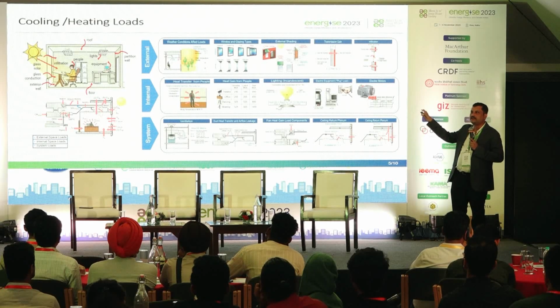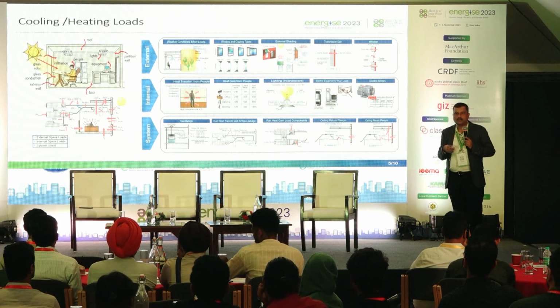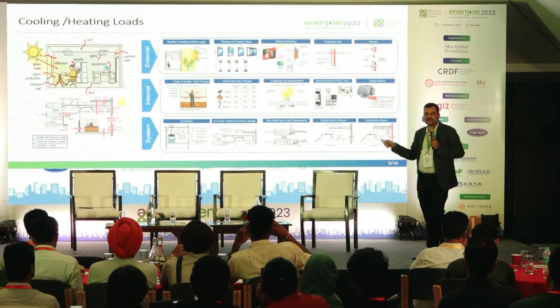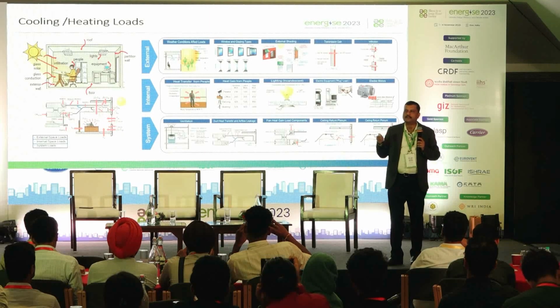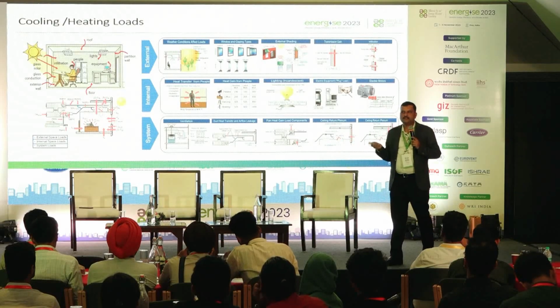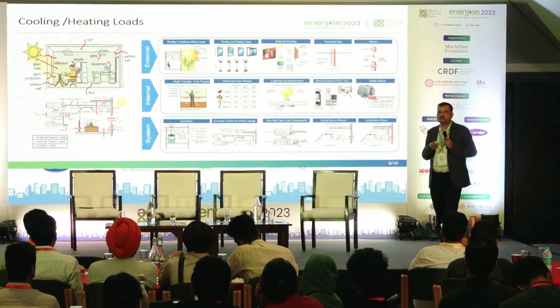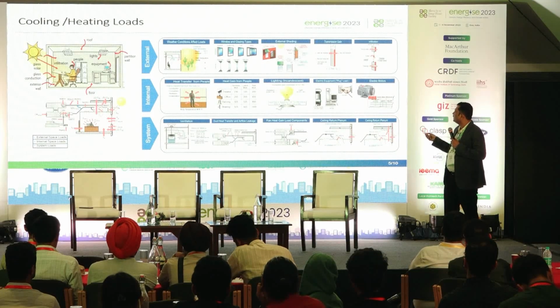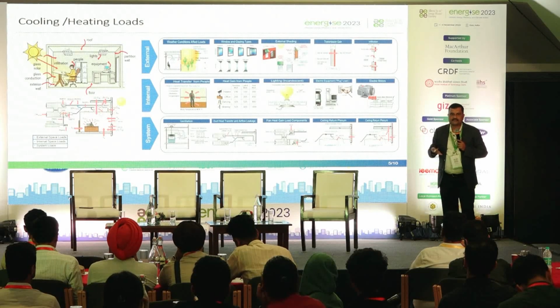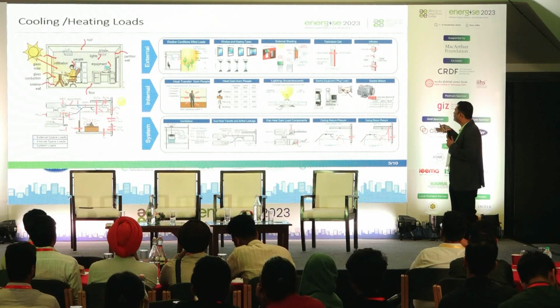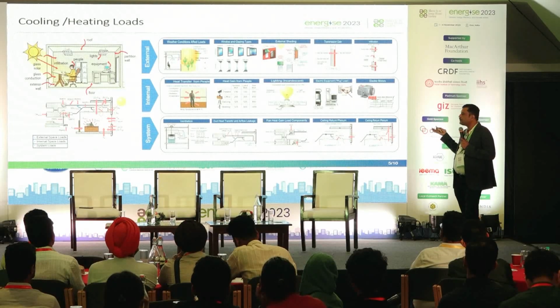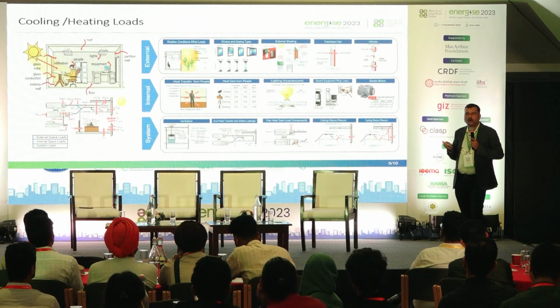One is, of course, the external things which none of us have control on. Your weather can go haywire. Take an example of Delhi: it can be chilling, it can be equally hot. So you need to design a system which works for both. The kind of glass you use, the kind of insulation used, shading coefficients, transmission, infiltration - all this will have an impact on the total cooling loads.